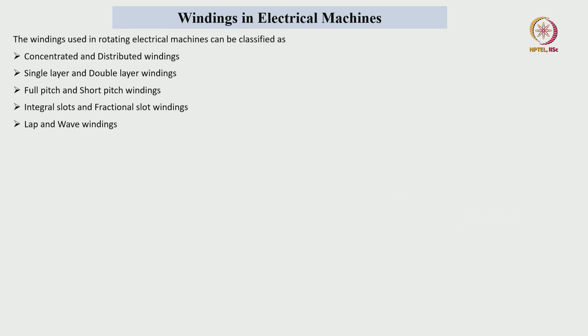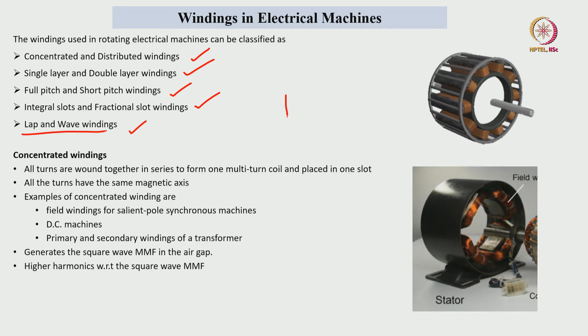The windings used in electrical machines are classified as concentrated and distributed windings, single layer and double layer windings, full pitch and short pitch windings, fractional slot and integral slot windings, lap winding and wave windings. Lap and wave windings are used in DC machines. In concentrated windings, all conductors are placed at one particular place — examples include inductors, transformers, DC machine field windings, and field windings of salient pole synchronous machines — and they generate a square type MMF waveform with higher harmonics.